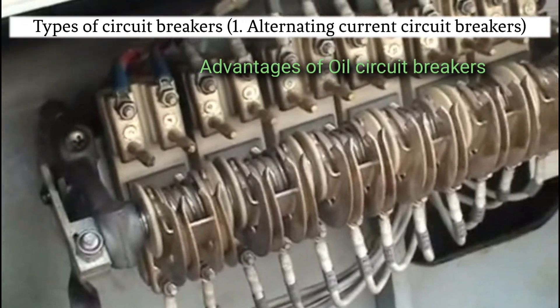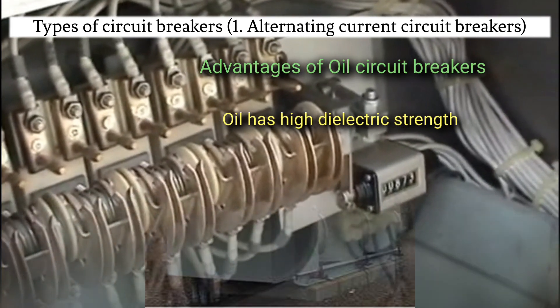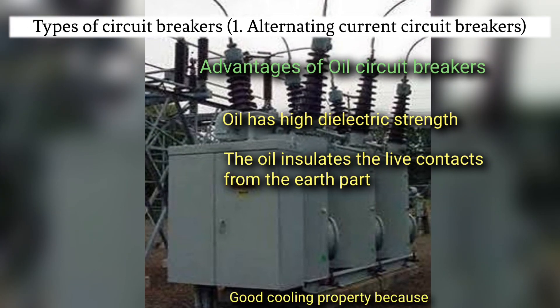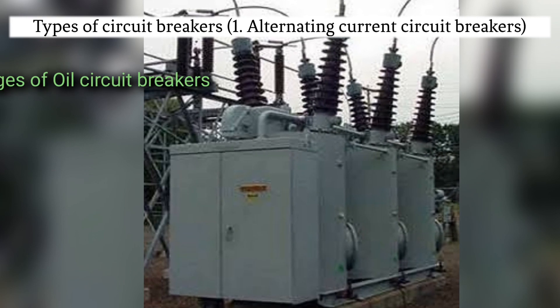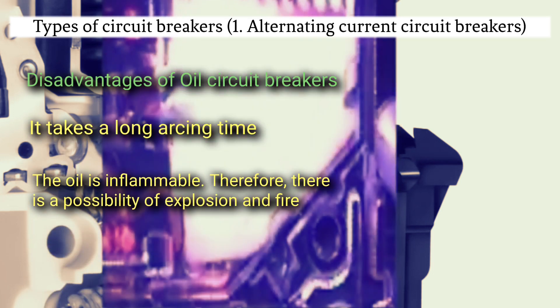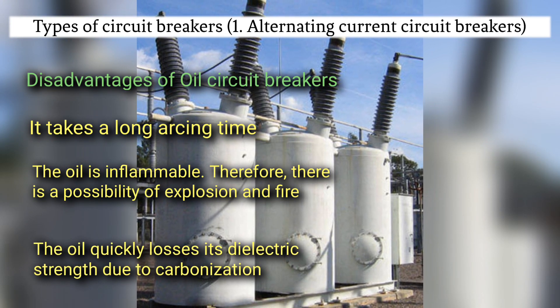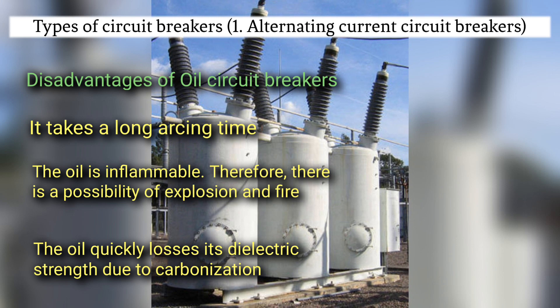Advantages of oil circuit breaker: oil has high dielectric strength; the oil insulates the live contacts from the earth parts; good cooling properties because of the decomposition. Disadvantages of oil circuit breakers: it takes a long arcing time; the oil is inflammable, therefore there is a possibility of explosion and fire; the oil quickly loses its dielectric strength due to carbonization.